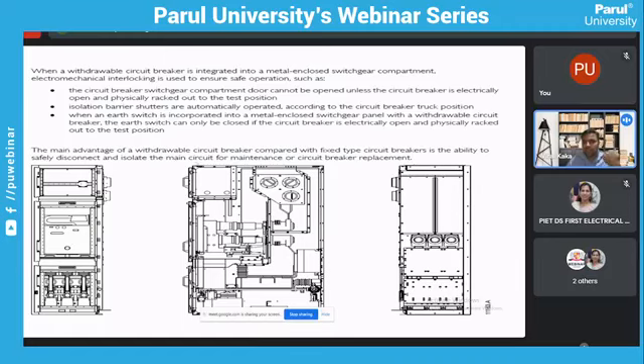Let's say you are doing any cable crimping or cable maintenance activity on a cable compartment. Irrespective of the bus bar being energized, you can still do that activity because there is a completely metallic partition in that area. But the practice is to have complete earthing on the cable side, and then do the maintenance activity on the cable. Your rest of the feeders or sections of the board can still remain live. So that was the point I was trying to make here.